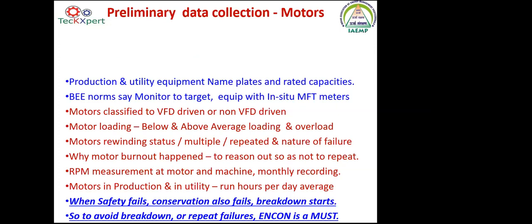The RPM measurement from the motor to the machine is a monthly recording to be done by you. I will discuss it at length later, but that is also important in terms of productivity for your given industry. So for the production machines and utility machines, the motors, especially the run hours, have to be available either in the OEM's console or you can retrofit it. And you know how many hours the motor has run.